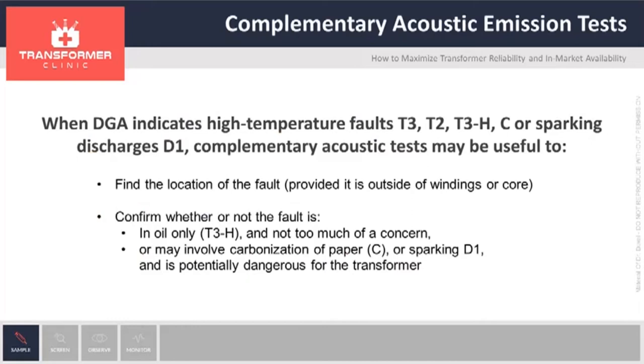When DGA indicates a high temperature fault T3, T2, T3 in oil, C, or electrical discharge D1, complementary acoustic tests may be very useful. First, to find the location of the fault, provided it is not inside the windings or core. And second, to confirm whether the fault is in oil only and therefore not too much of a concern, or it may involve carbonization of paper or discharges, and is potentially dangerous for the transformer.